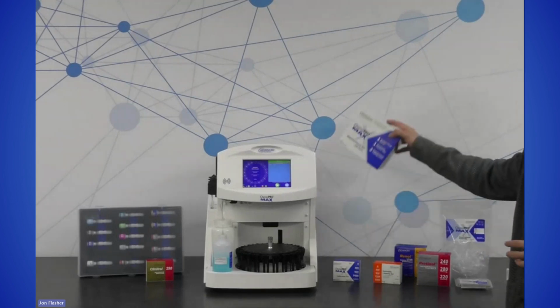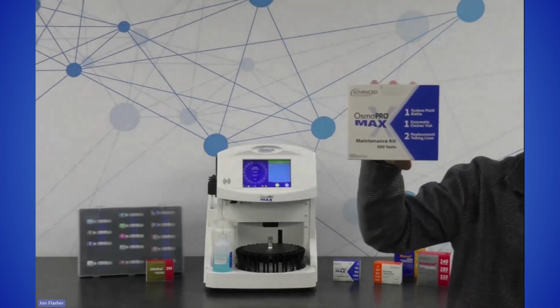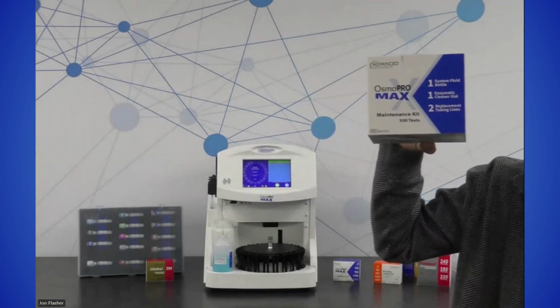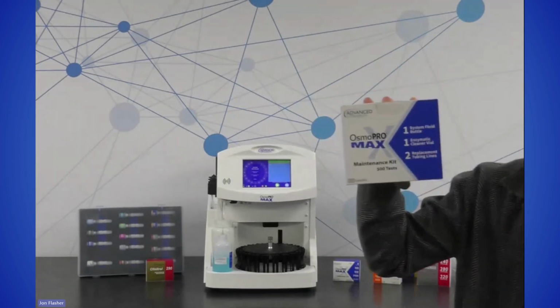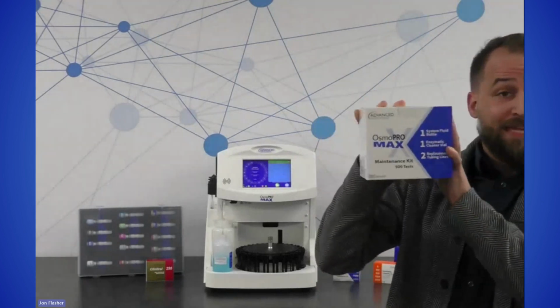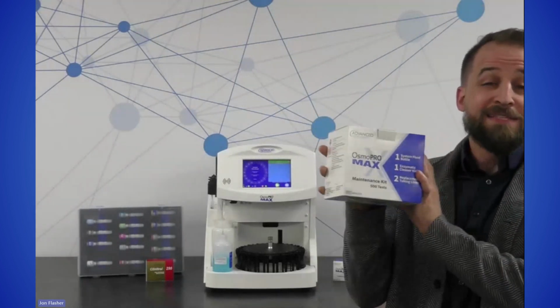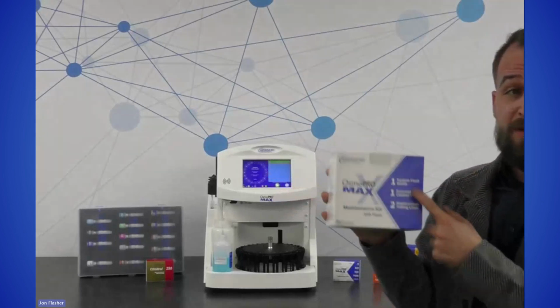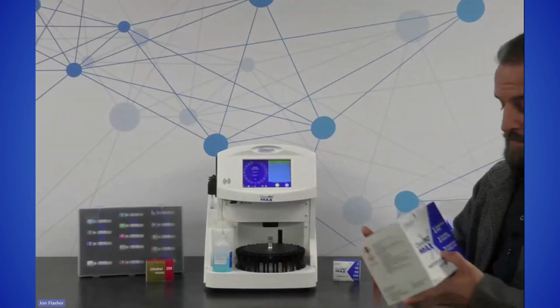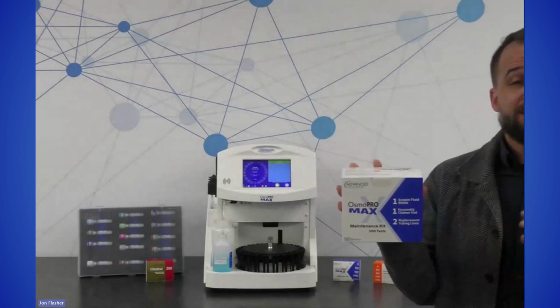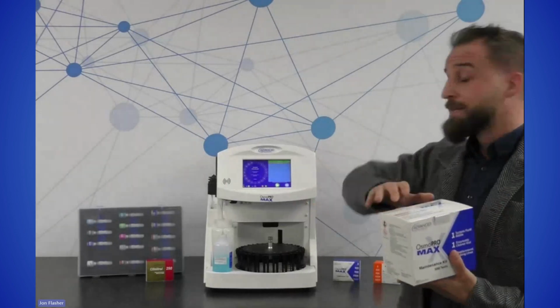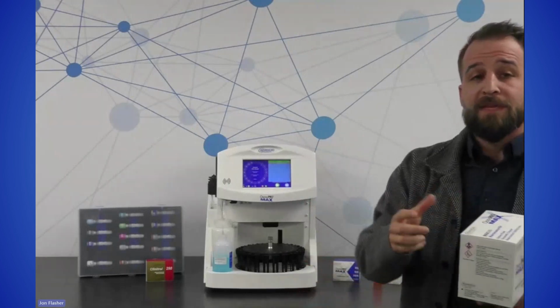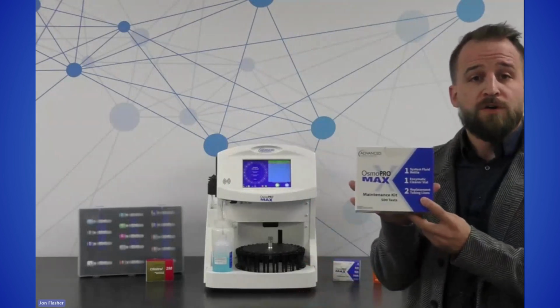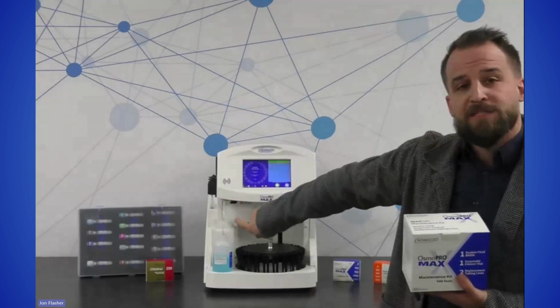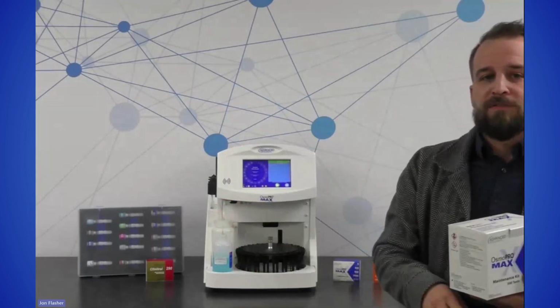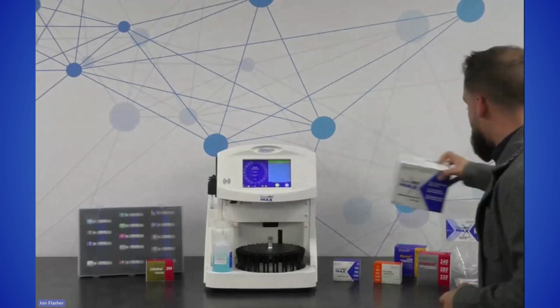So what does that mean? What does it come with? The primary consumable is this MAX 500 kit. Again, this instrument requires maintenance every 500 tests, and this is the kit that accommodates that maintenance. In this kit, you get one bottle of system fluid, so the little blue bottle of fluid down there. You get an enzymatic cleaner vial, a pepsin-based enzymatic cleaner that helps cleanse the fluidic pathway on the instrument. And you'll get two of those replacement tubes that, again, clip into place on the side of the instrument. I'll show you very briefly what that looks like later on in the demo.